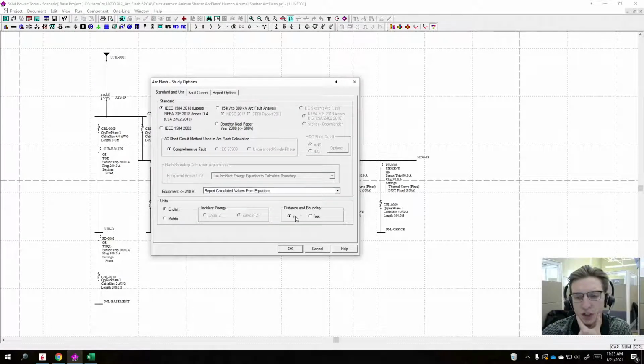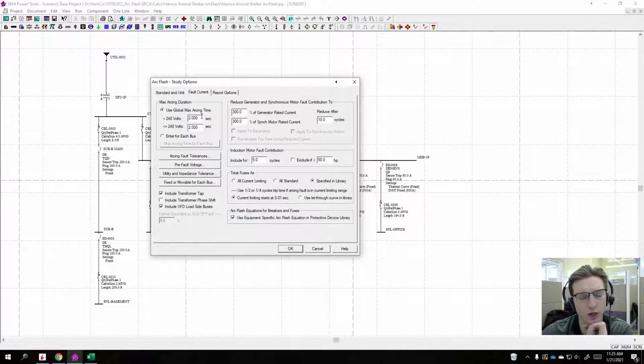Distance and boundaries, inches or feet, and then we'll come over here to fault current. We know the IEEE standards recommend that we cut off our calculation times for incident energy at 2 seconds. So if a breaker doesn't trip within 2 seconds, just go ahead and cut off the incident energy calculations. It's assumed that somebody would be able to get out of the way within 2 seconds, that they'd be able to react.